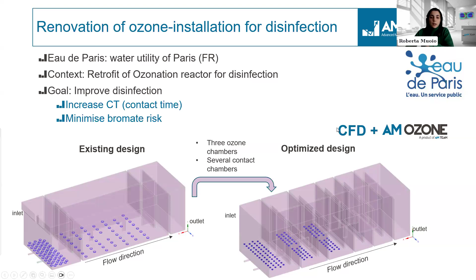In this slide, you can see the 3D concentration of dissolved ozone in the existing design and in the optimized design, as well as the bromate formation, so the concentration of bromate along the reactor. Basically, the main conclusion was that in the existing design, the ozone dose was not delivered optimally. There were gradients of ozone, so low ozone concentration and very high ozone concentration, especially in this second, very wide chamber where ozone is dosed. In the optimized design, we could avoid this and provide ozone in a more optimal way, which gives more uniform concentration of ozone along the reactor, while keeping the same bromate formation at the same dose.